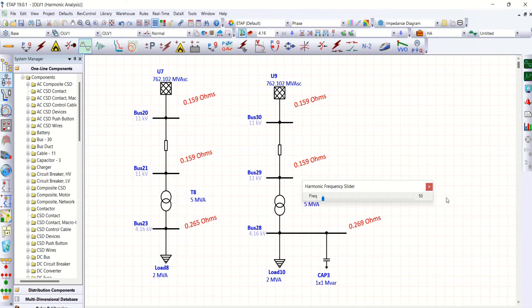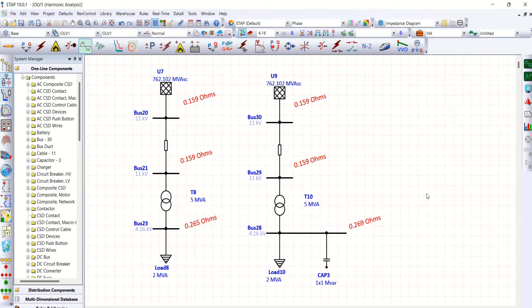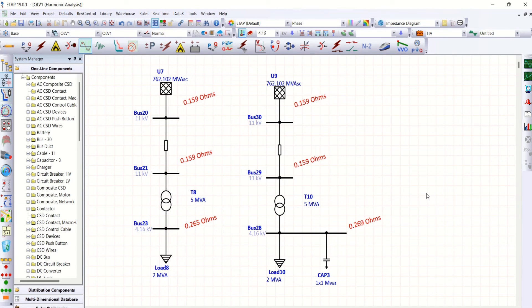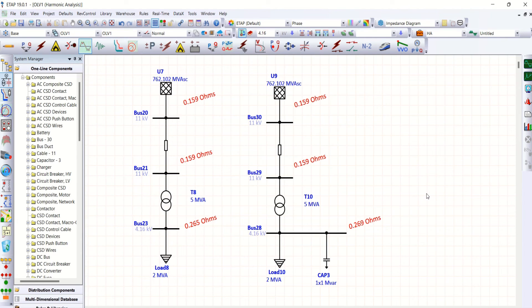So whenever the capacitor bank connected to the system, provided the system with harmonic load, it is mandatory to conduct harmonic analysis. Based on the harmonic analysis, harmonic filter should be designed.